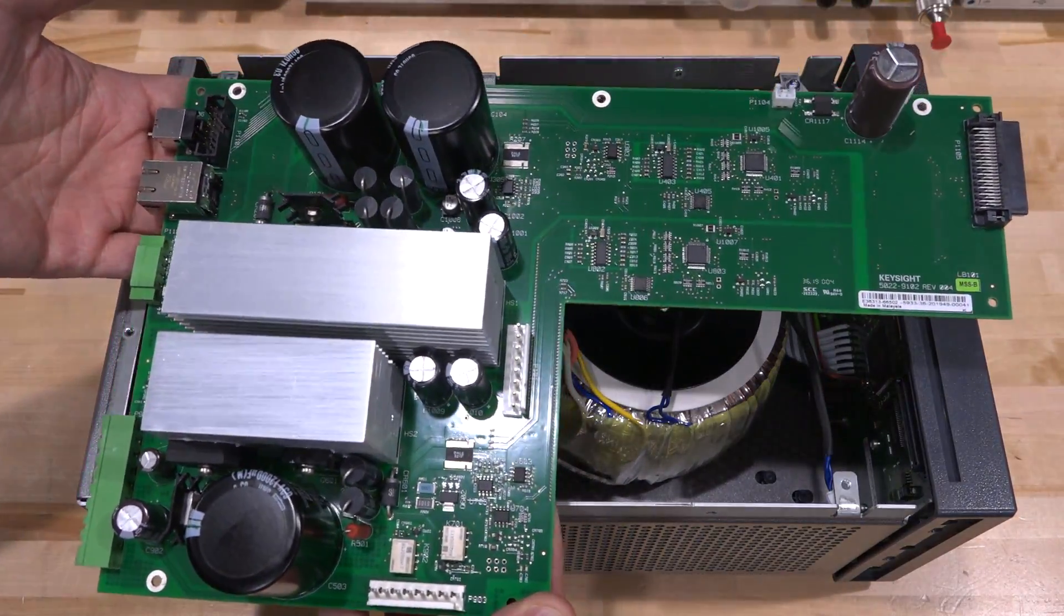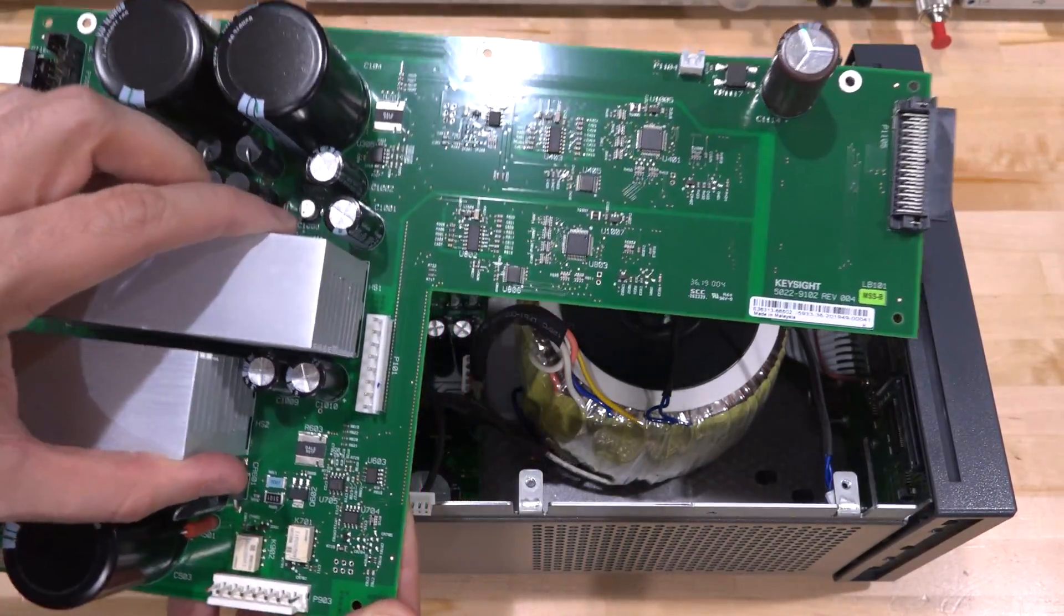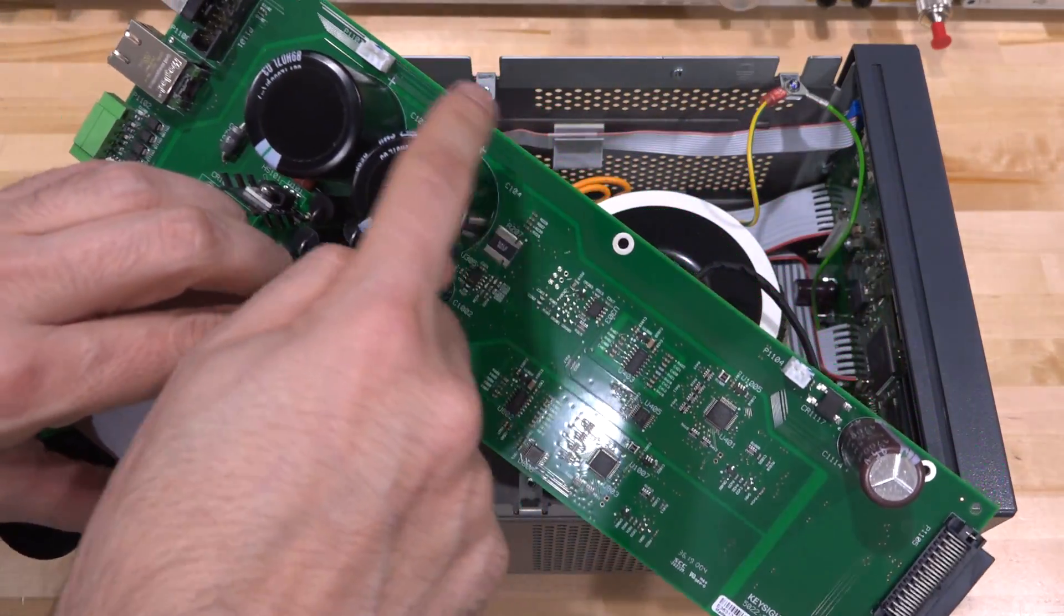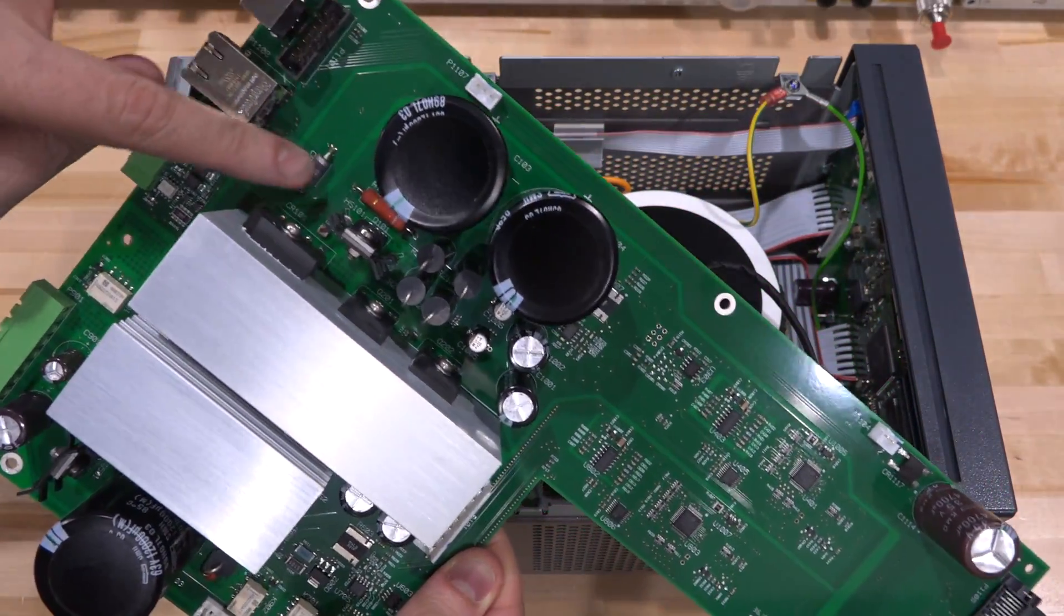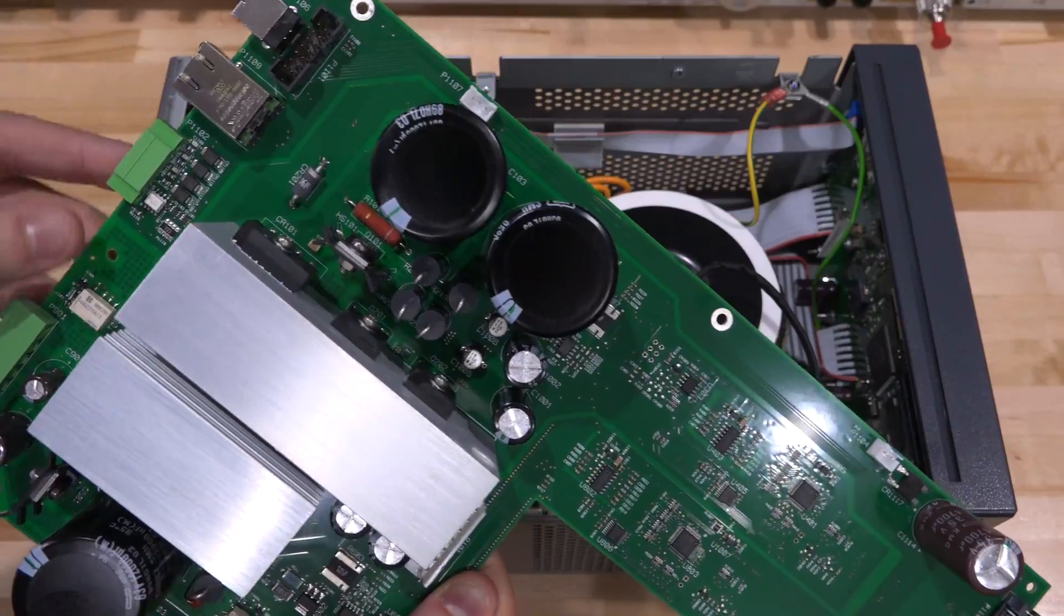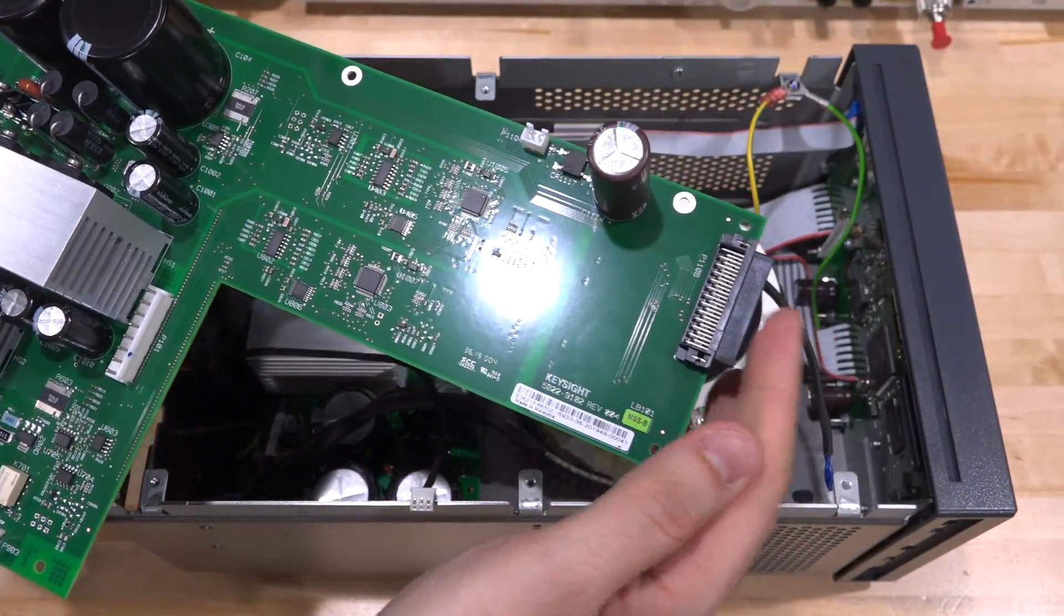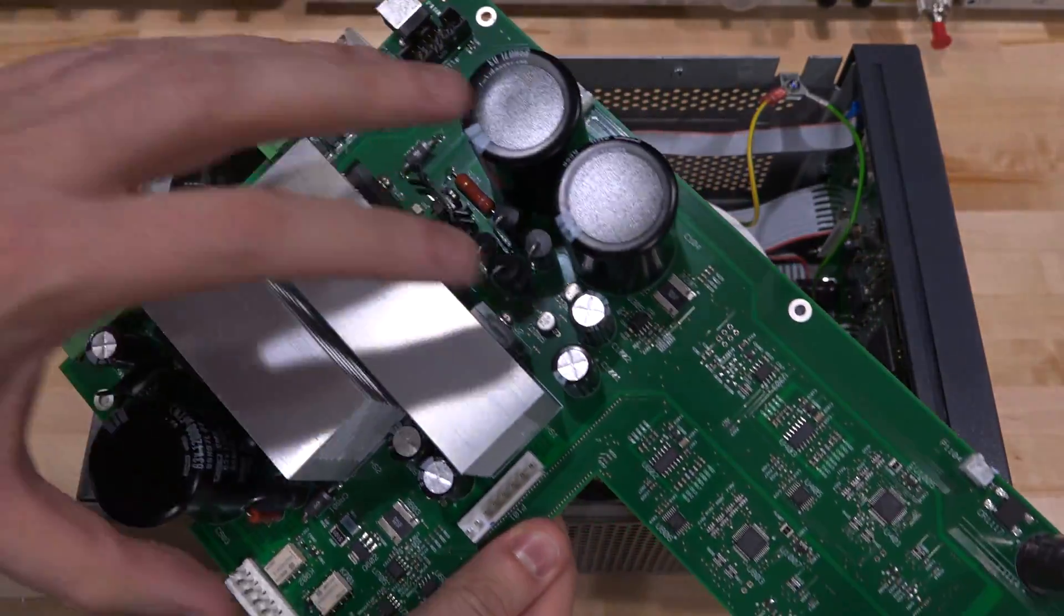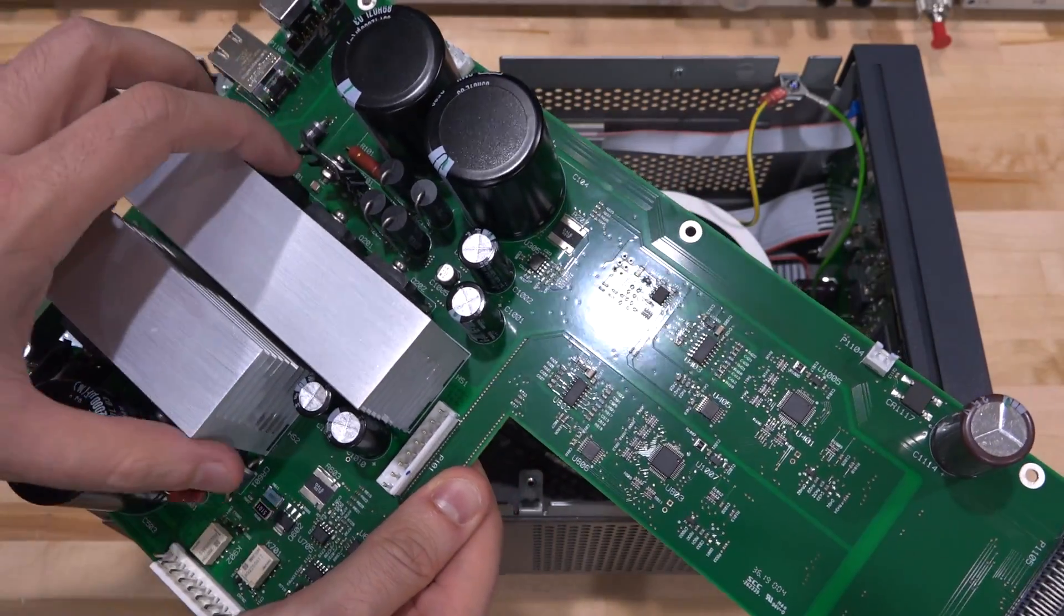All the computation, the GUI, everything is actually handled on this. There is really no digital processing on this interface at all, which is quite interesting too. You can see the separation clearly here and it goes all the way around and hugs all the human interface parts of this. Because this has the human interface from the front panel, this is all the ones in the back, so clearly the center is fully isolated.